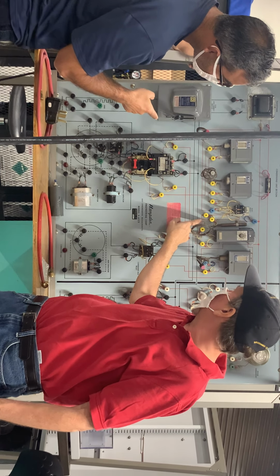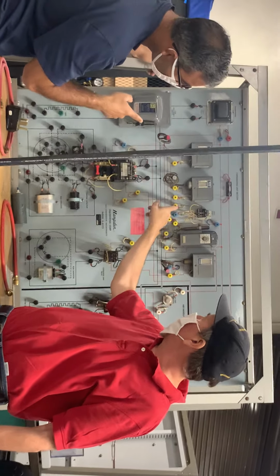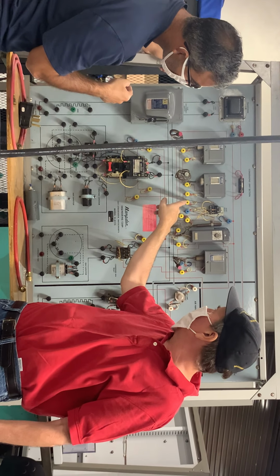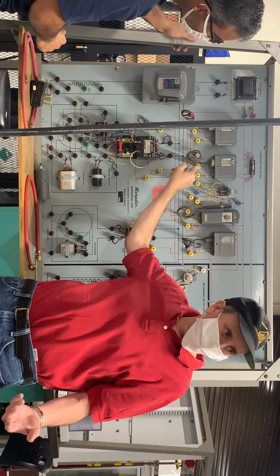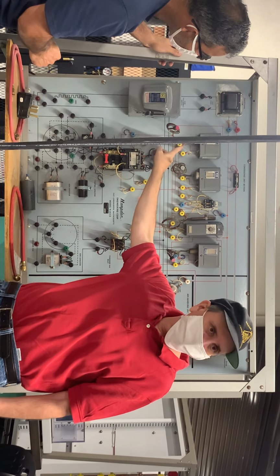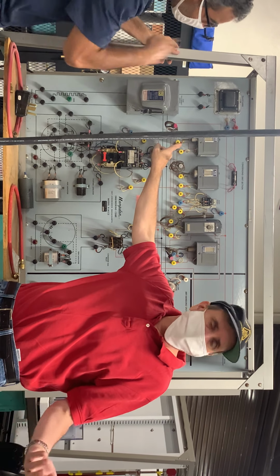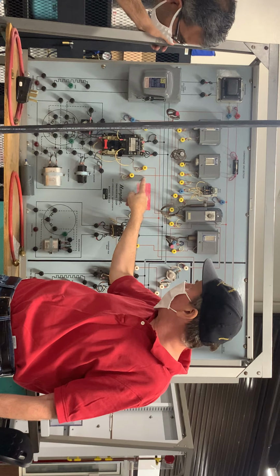So then we come up through here. No, I'm sorry, we go up this one through the contact of this reset relay. Then we go through the low pressure switch. That way if it loses refrigerant, it doesn't run. Then it goes to the high pressure switch, which if the condenser's dirty or something, it doesn't run. Then it comes back to this again.